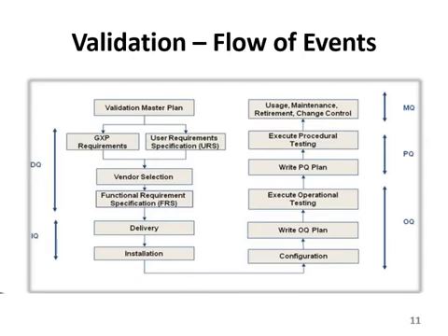Then is functional requirement specification. Now the next step, you have got the instrument. What you have to do is maintain the functional requirement specifications as well, that is, which functions are required by you. So you must have a clear specification of what functions are required in that instrument or in that equipment.